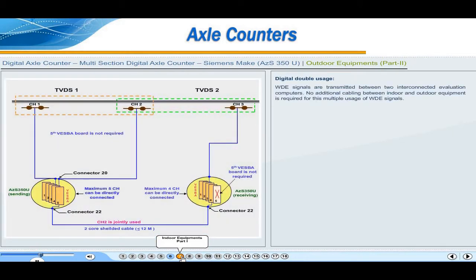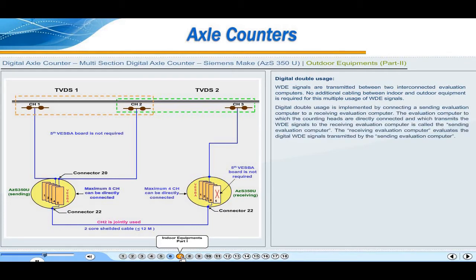Digital double usage. WDE signals are transmitted between two interconnected evaluation computers. No additional cabling between indoor and outdoor equipment is required for this multiple usage of WDE signals. Digital double usage is implemented by connecting a sending evaluation computer to a receiving evaluation computer. The evaluation computer, to which the counting heads are directly connected and which transmits the WDE signals to the receiving evaluation computer, is called the sending evaluation computer. The receiving evaluation computer evaluates the digital WDE signals transmitted by the sending evaluation computer.